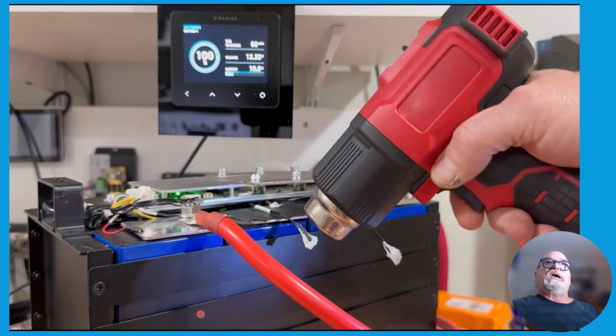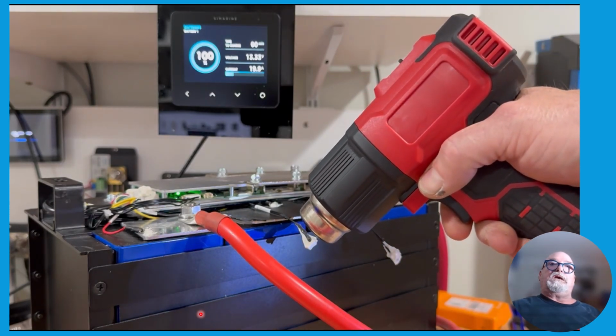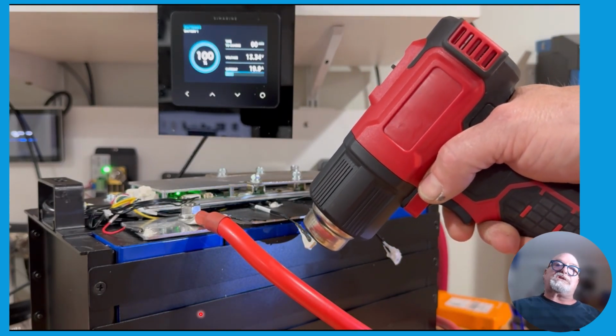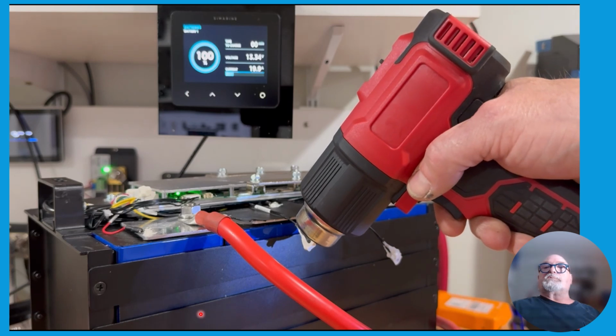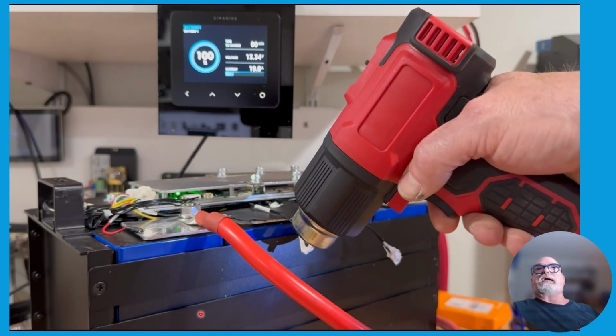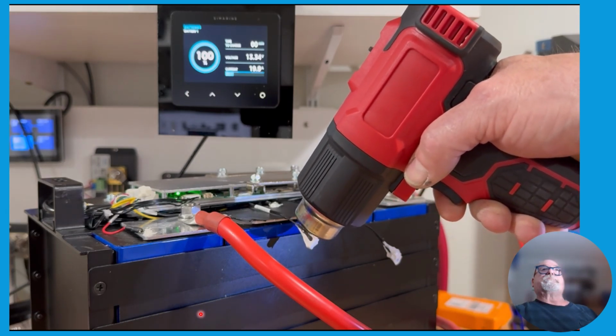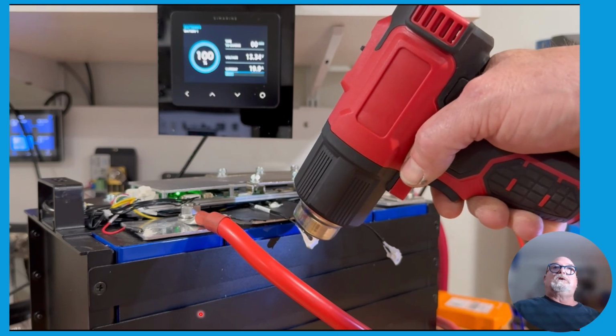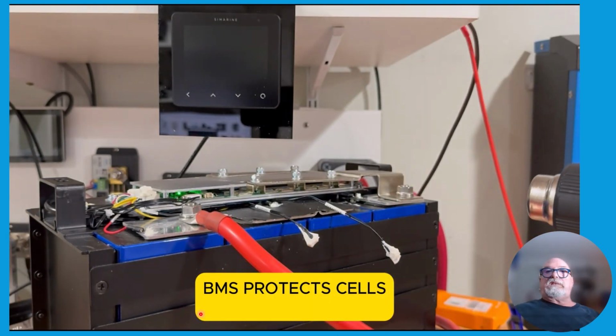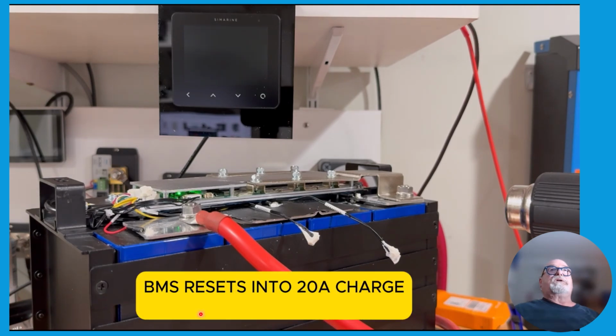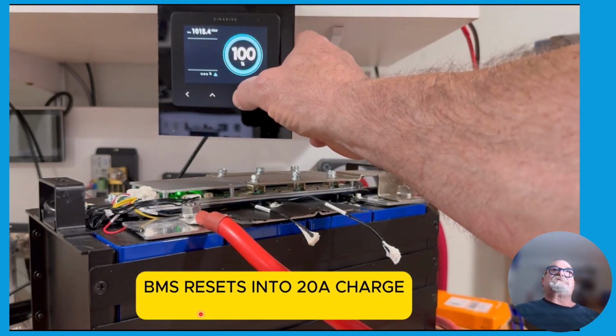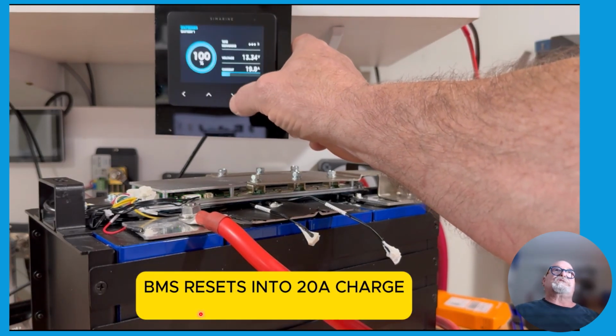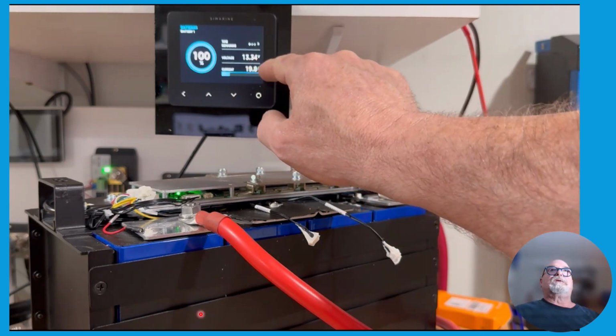Here I'm testing the heat protection to make sure the battery shuts off on over temp. Again we're going to see the battery monitor go blank because I'm heating it so hot. There we go - this again takes a few seconds to come back on, there it is, and again it reset into a 20 amp charge current. I just have to switch pages on the Simarine.